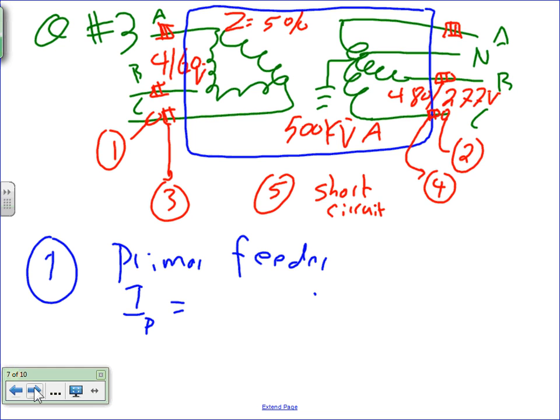The last question is a transformer. And my transformer guys have the following. I have a delta Y, the most common transformer. On the primary side, I have 4160 volt. On the secondary side, they have 480/277. The impedance is 5%, and the KVA size is 500. I need to size the following.